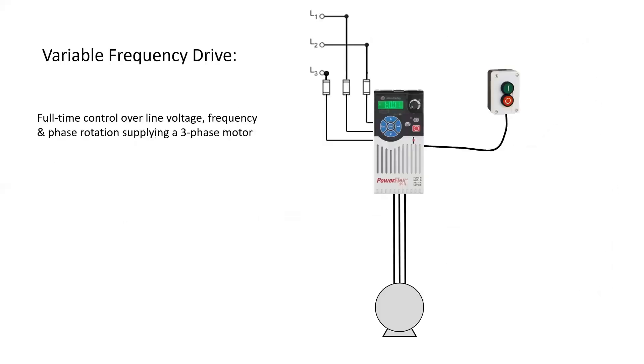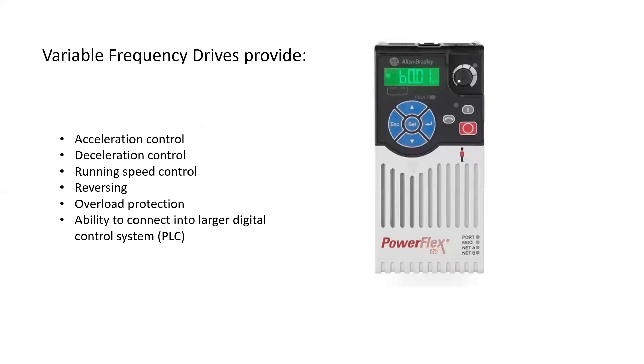A variable frequency drive has full-time control over line voltage, frequency, and phase rotation supplying a three-phase motor. Although it has push buttons on the front and a rotary dial to set the motor speed, often a separate push button station or further controls are utilized. A VFD provides acceleration control, deceleration control, running speed control, reversing, overload protection, and the ability to connect into larger digital control systems such as PLCs.